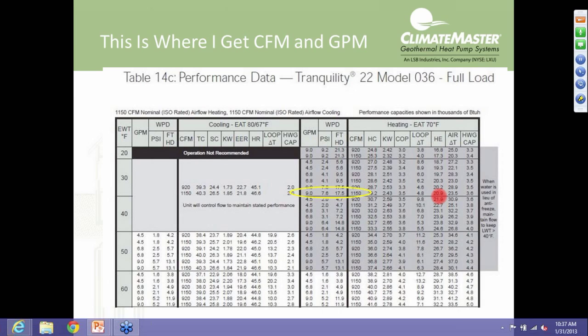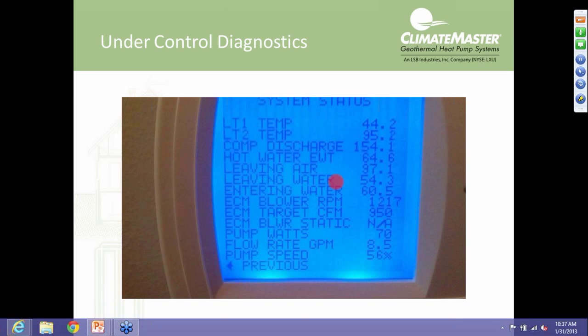Again, here looking at the screen, you can get your entering water and your leaving water temperatures. If we've got a variable speed pump running between 50 and 90%, we've got our GPM right here. And look at those pump watts. That's where this pump really shines. 70 watts. Holy cow, that is nice and low, isn't it? Again, we've got our GPM here, and our delta T right off the service tool or the communicating thermostat.